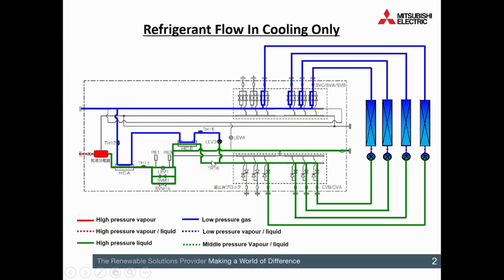Now, I'm being very careful with these numbers because we've got an inverter-driven compressor and we've got an inverter-driven fan. So these temperatures are going to fluctuate. And the way that we're controlling this is via LEV3. So LEV3 is being used to bleed off some of the refrigerant that should be going to the indoor units and passing it through that tube-in-tube heat exchanger to subcool it. So that's the idea. And when it's doing this, LEV1 will be wide open because it's on full-on cooling, and these valves will be open as well.